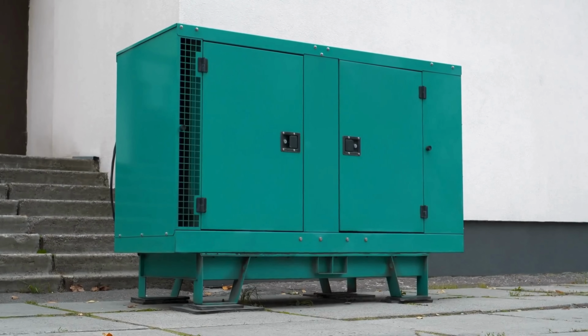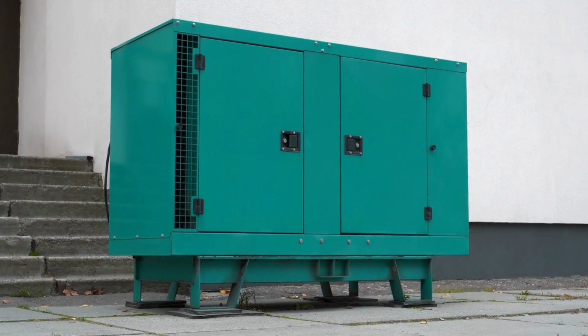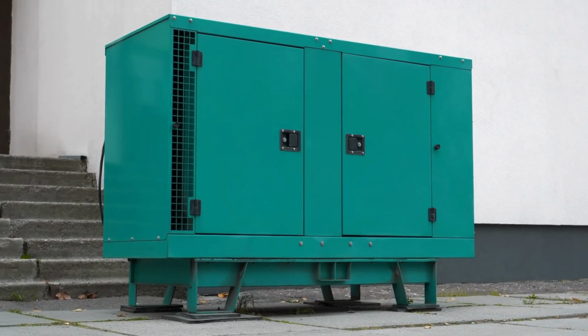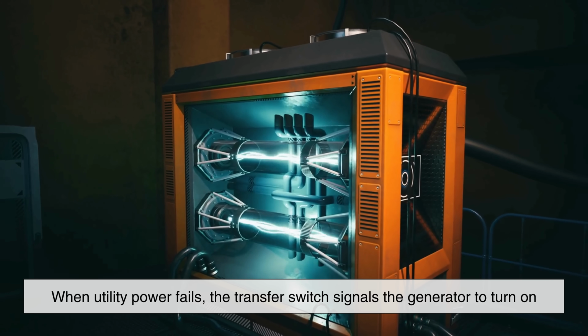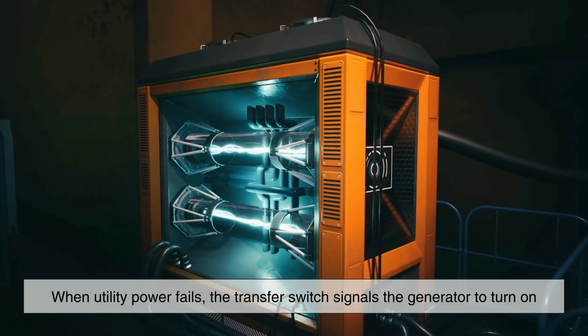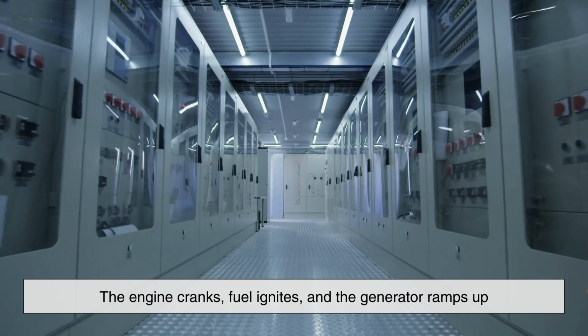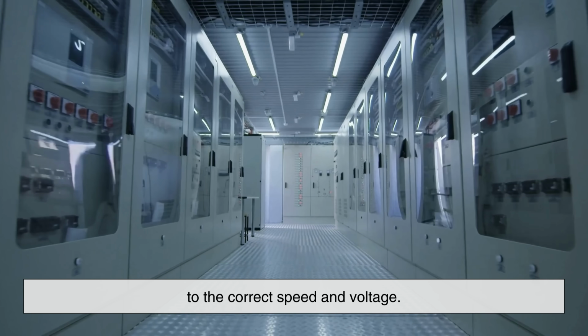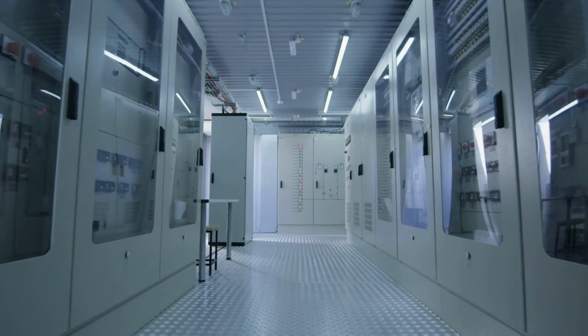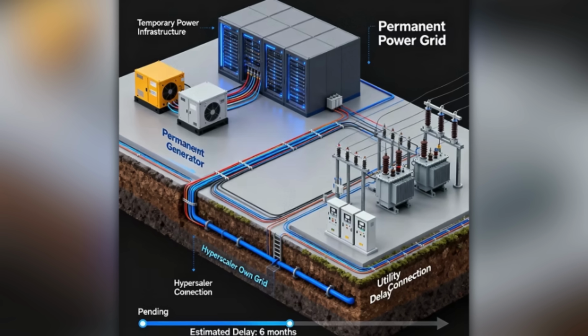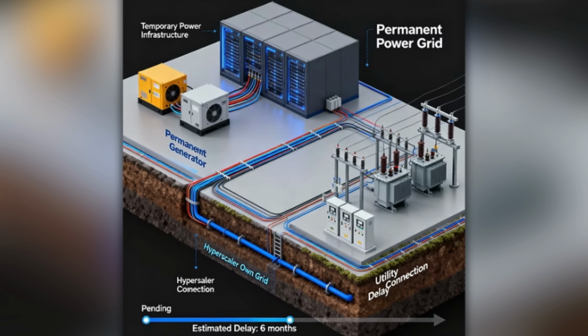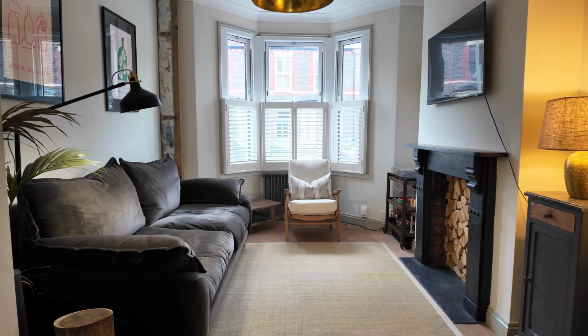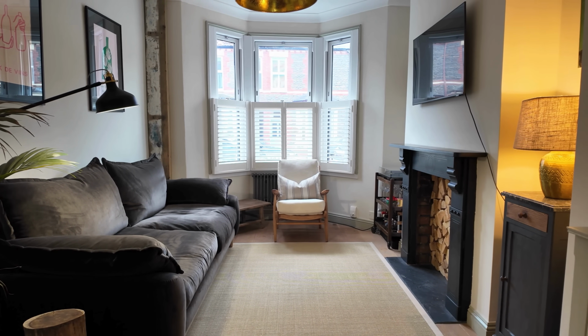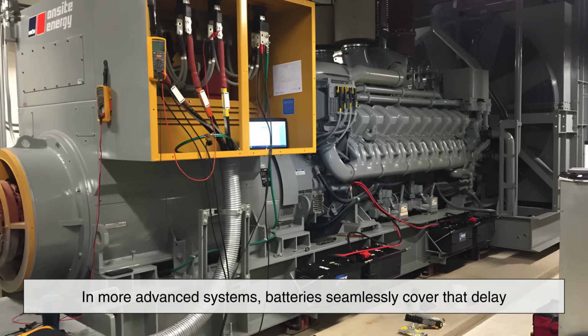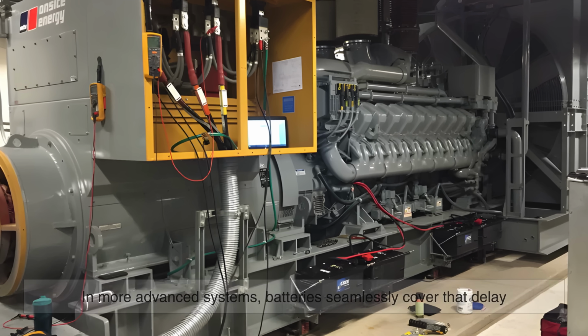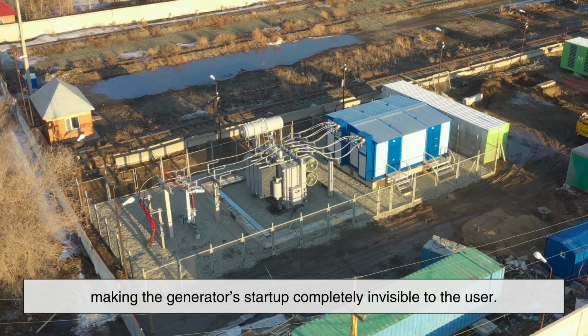Generators introduce a slightly different story. Unlike batteries, generators cannot supply power instantly because they must physically start an engine. When utility power fails, the transfer switch signals the generator to turn on. The engine cranks, fuel ignites, and the generator ramps up to the correct speed and voltage. This process typically takes a few seconds. During that short gap, either power is temporarily lost, or a battery system bridges the gap until the generator is ready. In homes without a UPS, you might notice a brief blackout of 2 to 10 seconds. In more advanced systems, batteries seamlessly cover that delay, making the generator's startup completely invisible to the user.